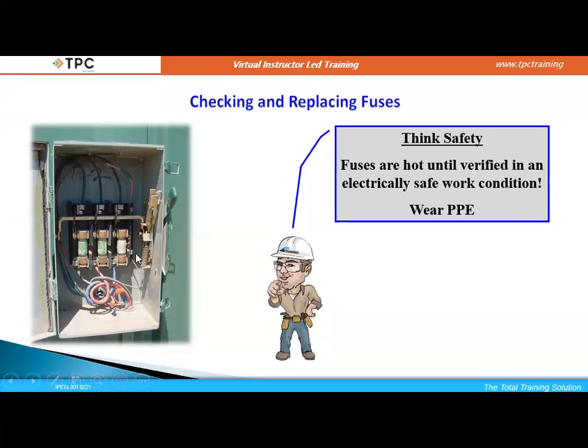Once I have determined that there is no voltage present here, I will get an insulated fuse puller, pull these out, and I will find out if it says 0 ohms and the fuse is good, or I will find out if the meter says OL, open line, and the fuse is bad.